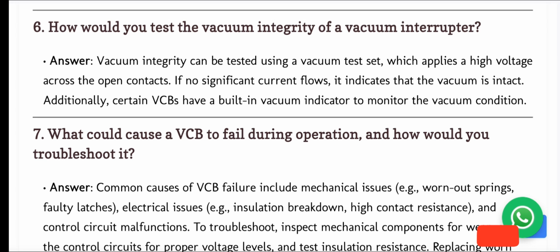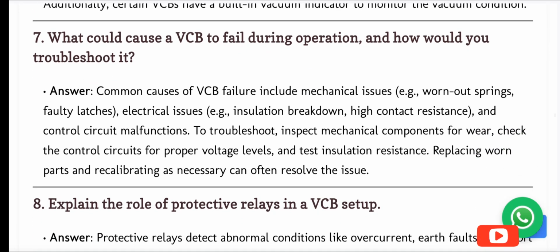Answer. Vacuum integrity can be tested using a vacuum test set, which applies a high voltage across the open contacts. If no significant current flows, it indicates that the vacuum is intact. Additionally, certain VCBs have a built-in vacuum indicator to monitor the vacuum condition. 7. What could cause a VCB to fail during operation, and how would you troubleshoot it?